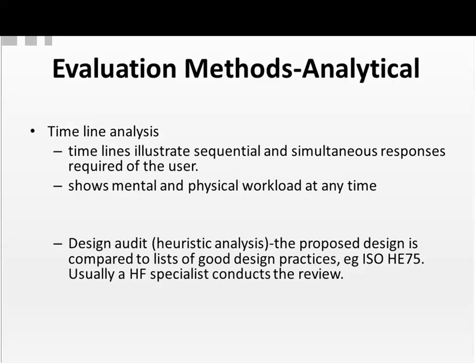You can do a timeline analysis. This is important for complex systems. The timelines illustrate the sequential and the simultaneous responses required of the user. It shows the mental and the physical workload at any time. By doing this analysis, you'll discover if the user is faced with doing 4 or 5 tasks at more or less the same time, which could overwhelm him.